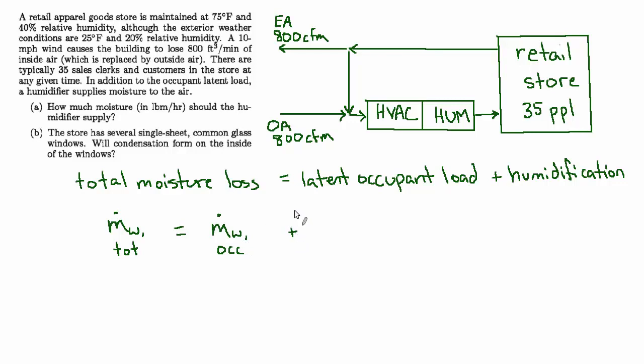Plus the mass flow rate of humidification—how much water vapor are we adding to the air? So again, ṁ_water of the humidification system. So we'll specify the occupant latent load first, and then we'll calculate the total moisture loss, and then we'll subtract and find the humidification load.